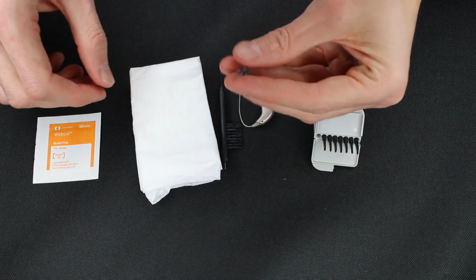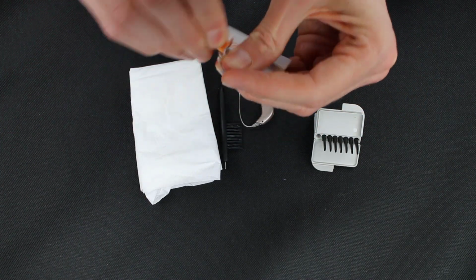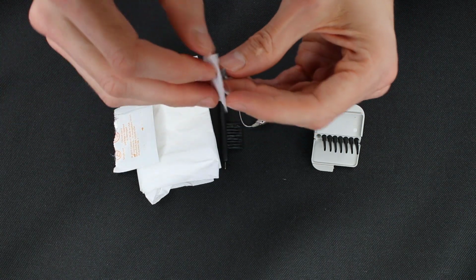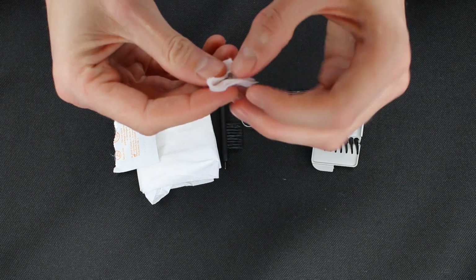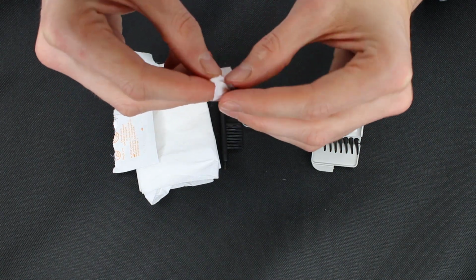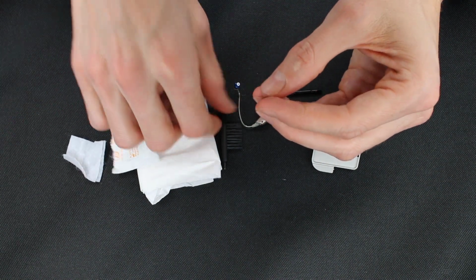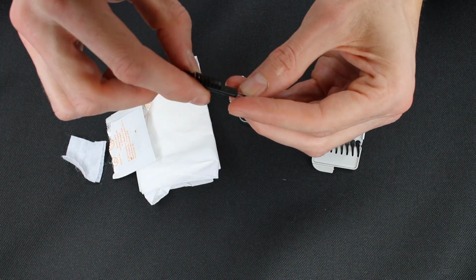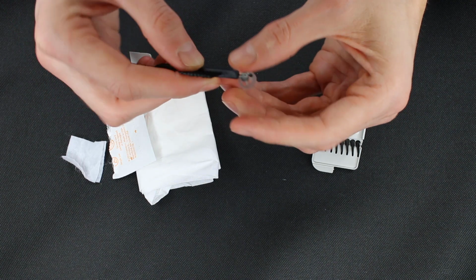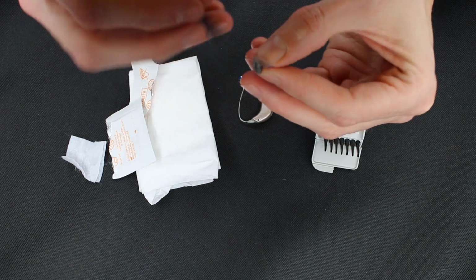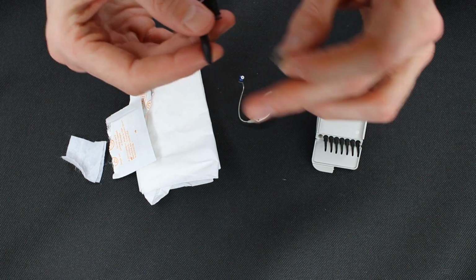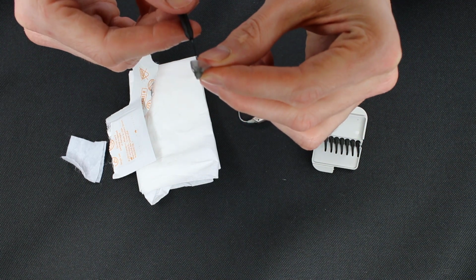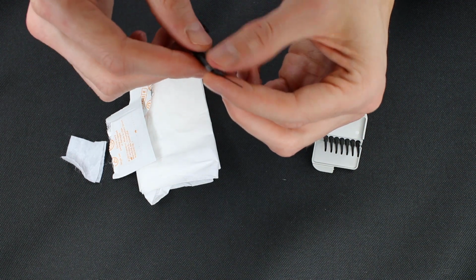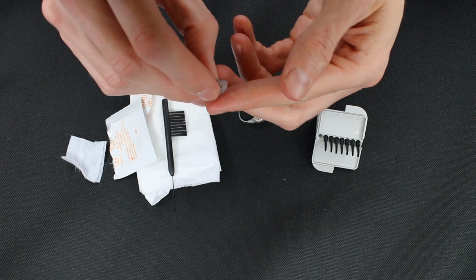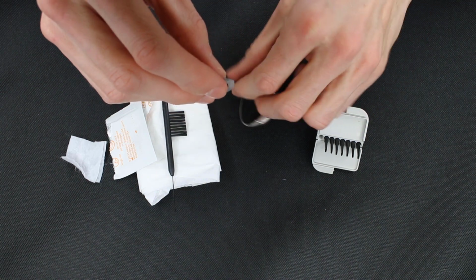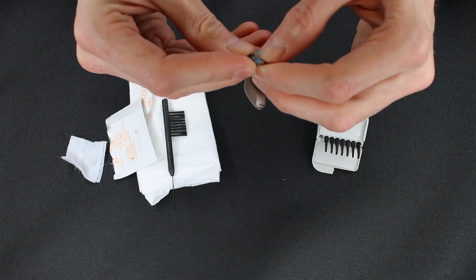Lastly, what we want to do is clean the dome. And when we're cleaning the dome, we can take an alcohol swab and make sure that we get all the earwax off of it. If you don't have an alcohol swab, you can also use a Kleenex for this. And then I always like to take either the wire tip of the cleaning tool and push it through the tip of the dome to make sure there's no wax in there. And we can even take the wire end here and stick it through to make sure all the earwax is out. You can also just replace these domes altogether if you need to. And then we're going to push it right back over the top.